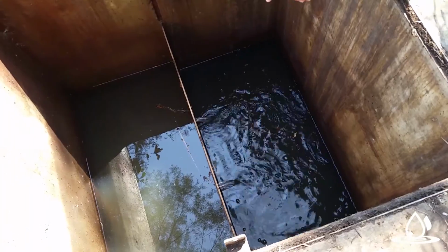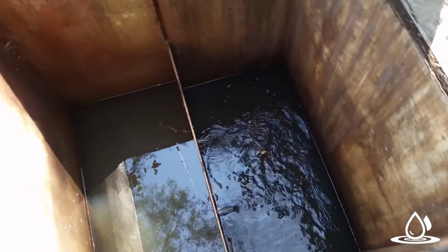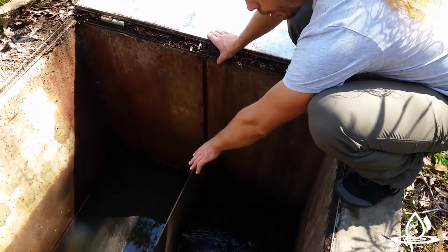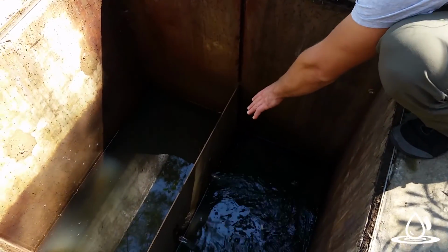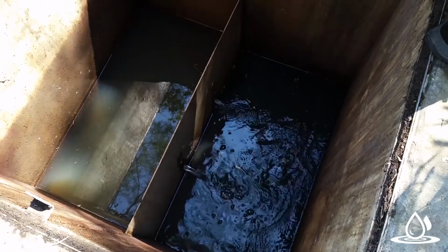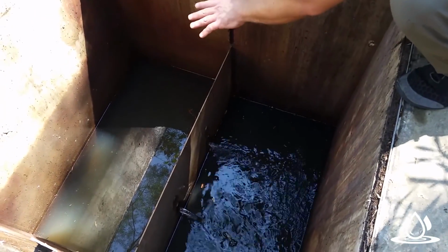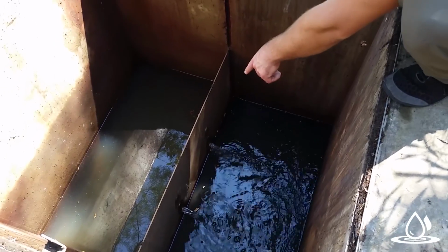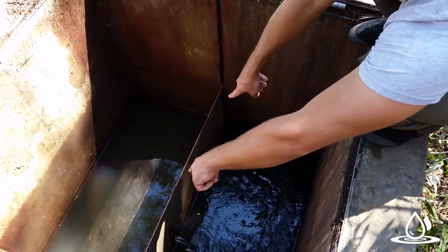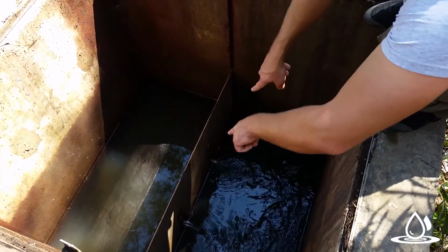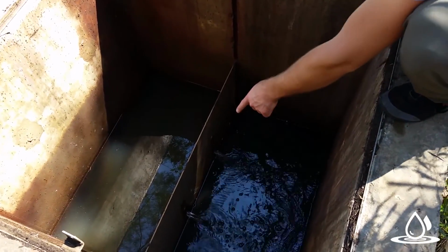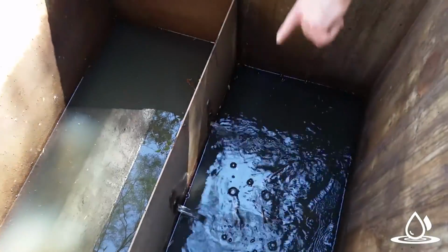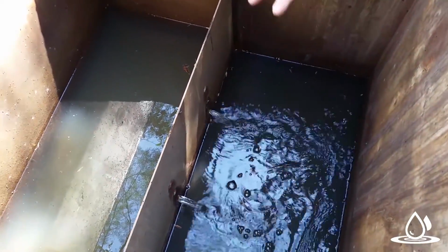So what is meant to happen here, you can hopefully see that there is this plate across the pit. That plate extends, you can see the top of it in shot there, all the way down to the base of the pit. It is sealed in on the sides and on the base, so it holds water back. But obviously there's a few holes drilled in this because you can see water pouring through. There are 2 rows of holes, here and here, and there are 4 holes in each. You can see the hole where the water's coming out. There is 1 hole below that on each side and 2 holes above it, for a total of 4 holes on each side.